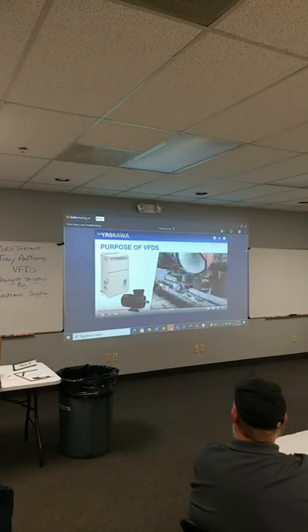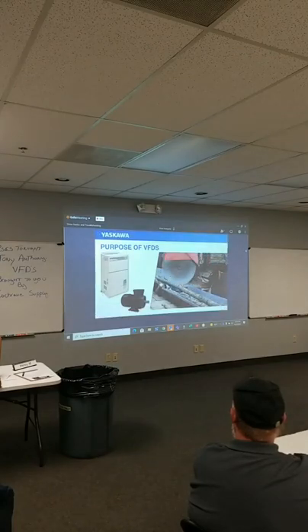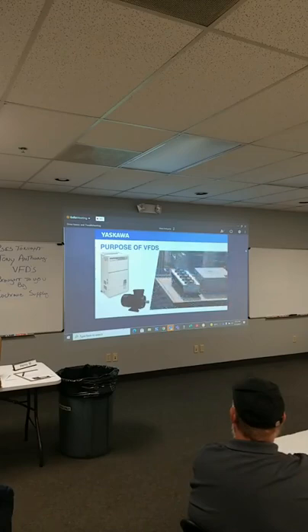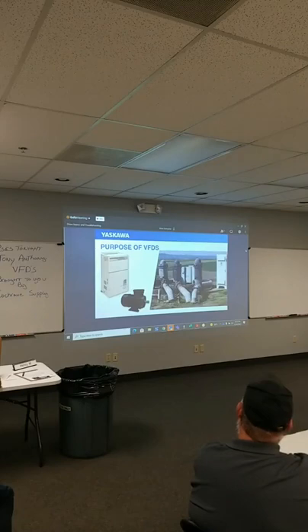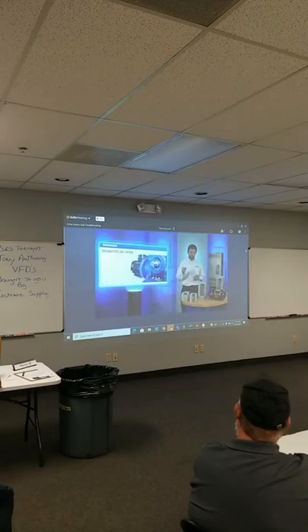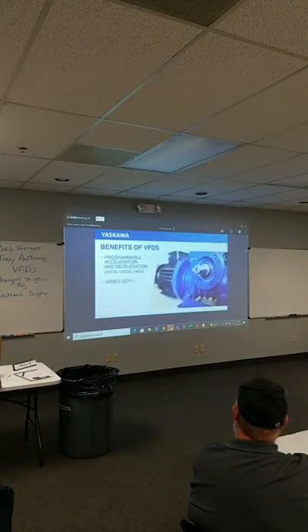Having full torque available allows us to use a standard or a general purpose motor in many more applications and situations than we would otherwise be able to. Furthermore, we can limit the output torque of a motor for a given application or point in the process should it be required. Since we now can control the motor, we can program our own acceleration and deceleration, or accel and decel times. Now, this will vary depending on the application.